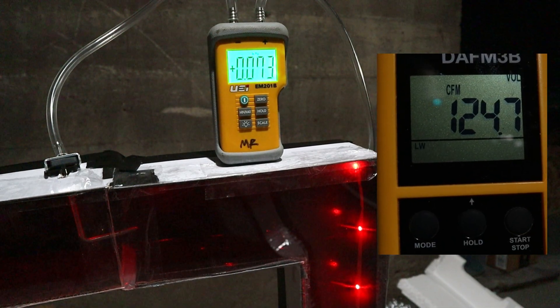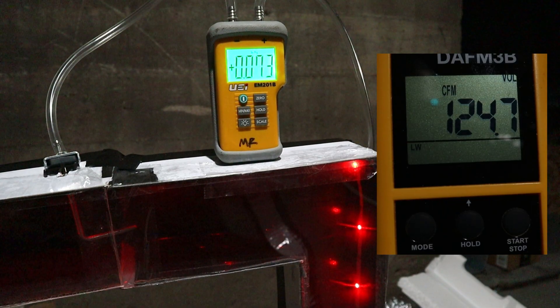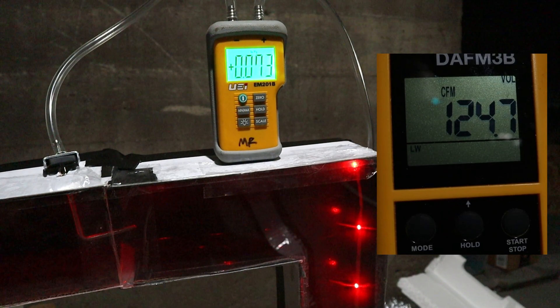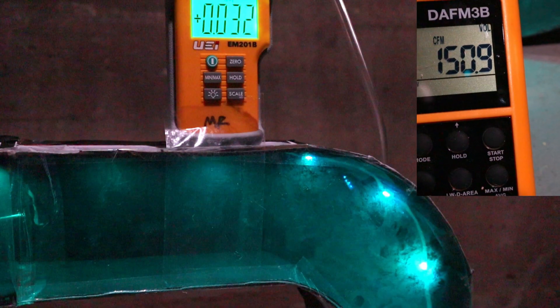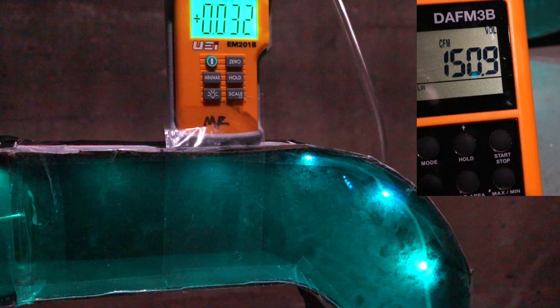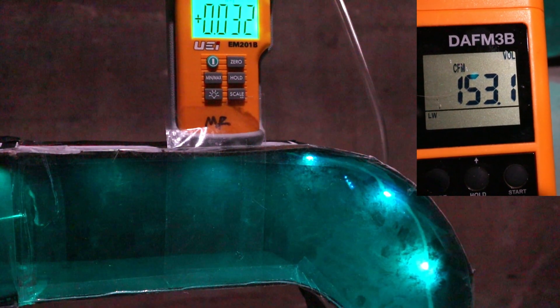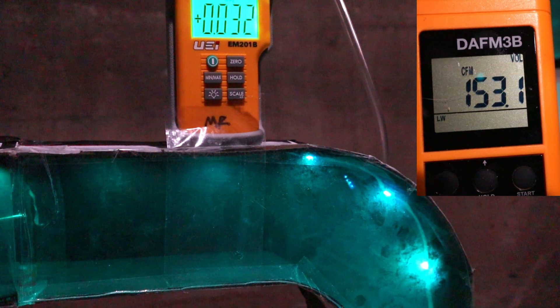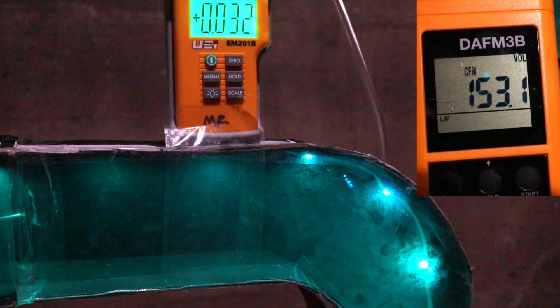What we just saw with our eyes we can also see on our tools. On a manometer, the hard 90 reads 0.073 inches of water column, and airflow out of that duct is about 120 to 125 CFMs. On the soft radius 90, it's a completely different story: static pressure is less than half at 0.032 inches, and airflow is increased to around 150 CFMs.